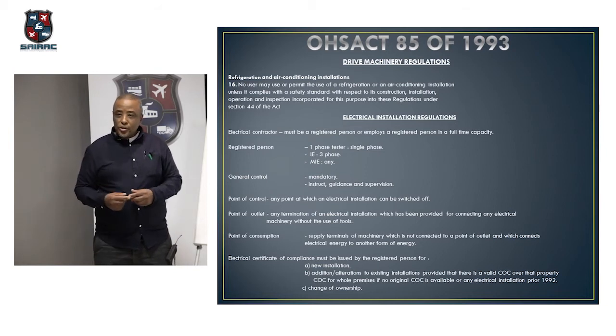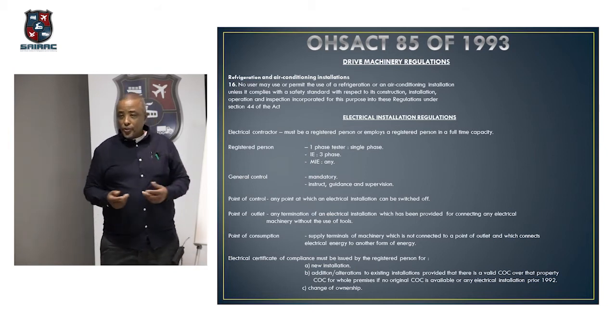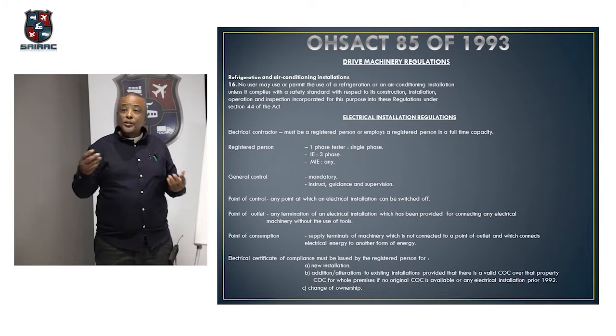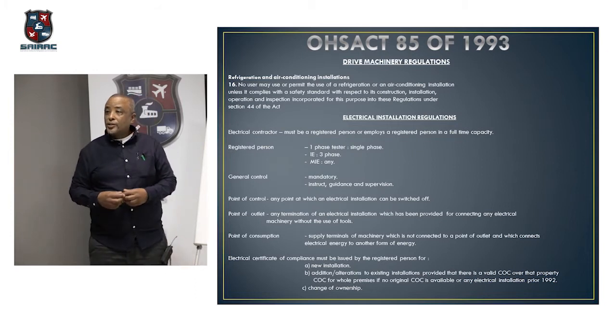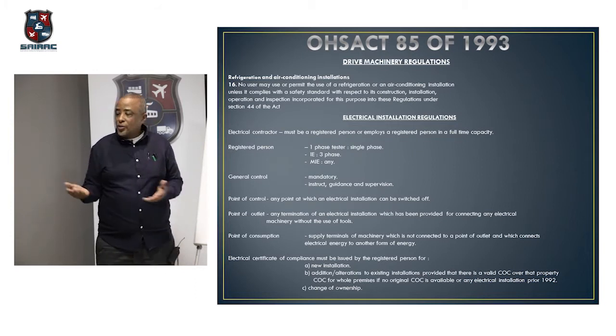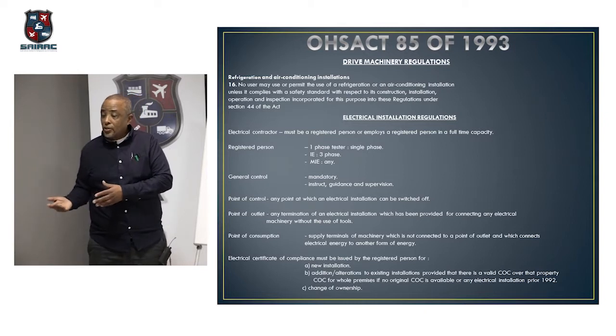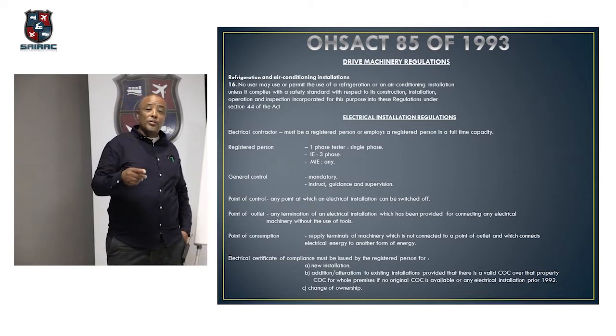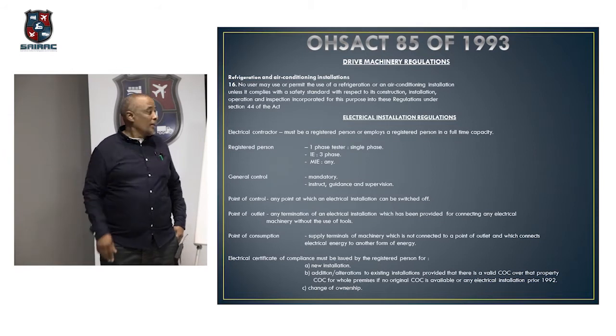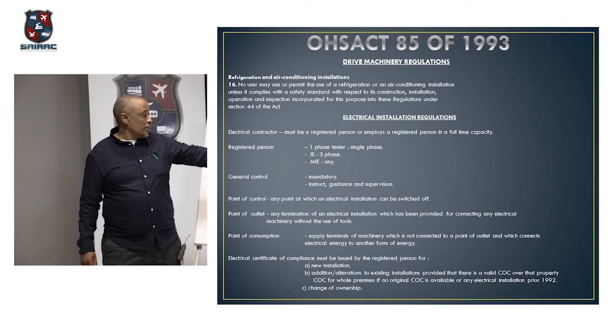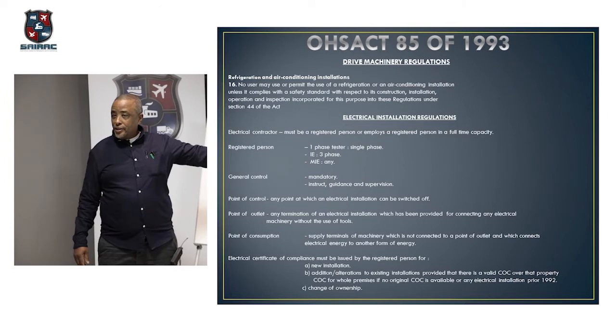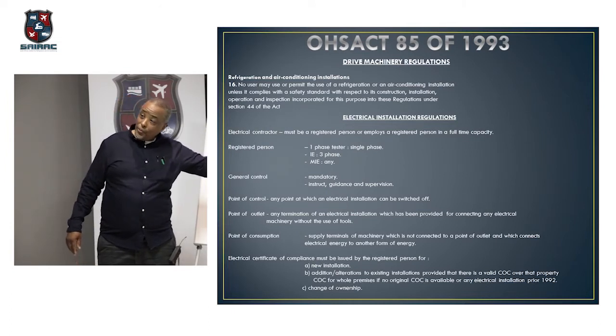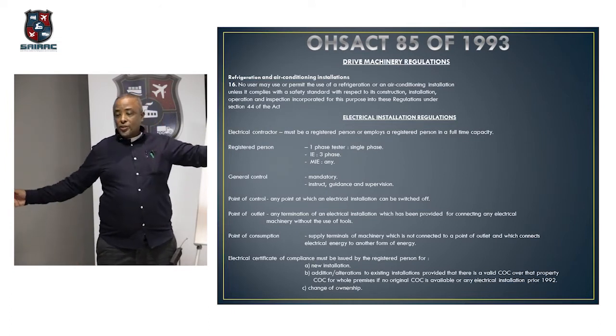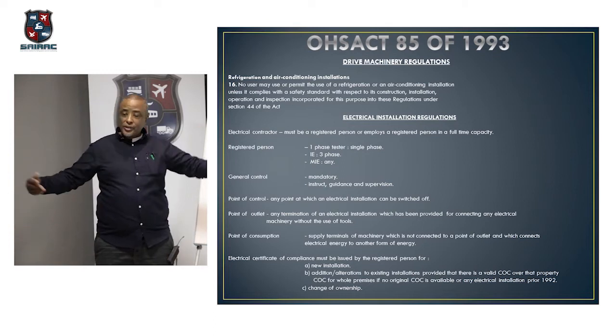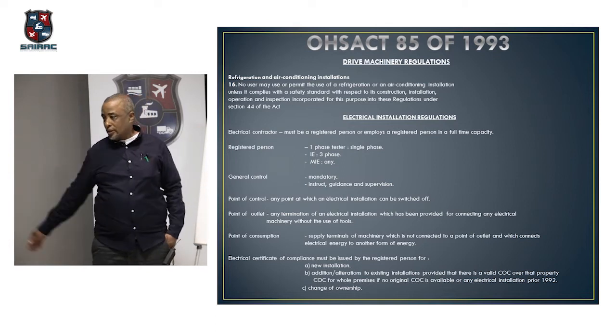The right way to do it is to ask the guy, do you have a COC for the property or for the business or for whatever it is? And they say no. As soon as they say no, well, I can't give you a COC, I can't even do the work legally. Okay, because as soon as you give a COC, you've got to give a COC for the whole thing. And that's also in the electrical installation regulations. It also says prior to 1992, there were no certificates of compliance. So if you do any alteration work to that type of premises, you'll issue a certificate for the whole installation.